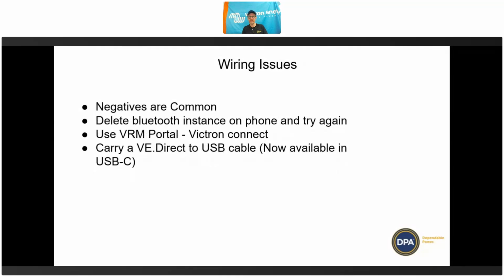Wiring issues - the common one I see is with the negatives being common. Looking at the small ones with the 6 connections, all the negatives are connected, and it does its switching on the positives. Every now and again somebody will assume it switches on the negative, like old PWM ones do, and they'll bypass the positive, putting all the positives together and connecting it to the negative - that just means it's not operating.